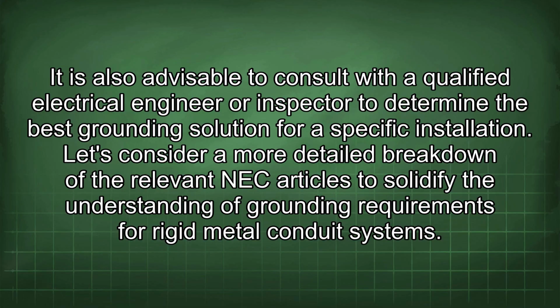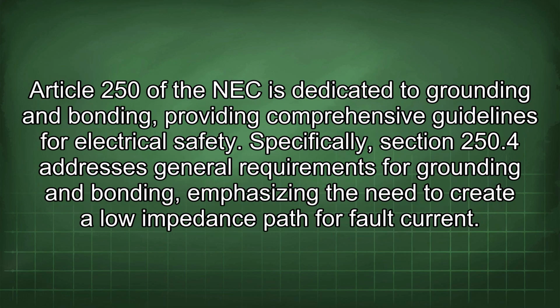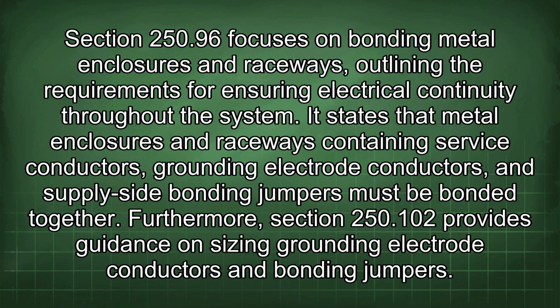Let's consider a more detailed breakdown of the relevant NEC articles to solidify the understanding of grounding requirements for rigid metal conduit systems. Article 250 of the NEC is dedicated to grounding and bonding, providing comprehensive guidelines for electrical safety. Specifically, Section 250.4 addresses general requirements for grounding and bonding, emphasizing the need to create a low impedance path for fault current. Section 250.96 focuses on bonding metal enclosures and raceways, outlining the requirements for ensuring electrical continuity throughout the system.